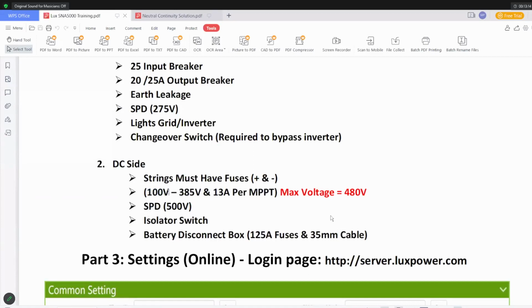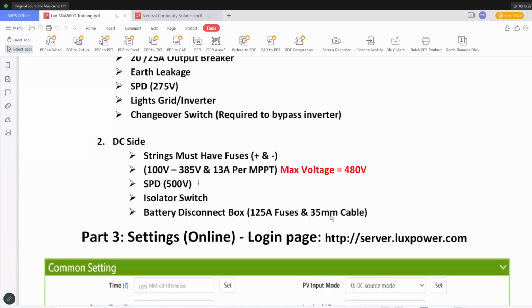The minimum voltage from your panels has to be a minimum of 120 volts, otherwise the inverter will not read any power coming from the panels. The max voltage is 480 volts, with 385 recommended, as stated in the diagram. An SPD of 500 volts is also recommended on the DC side.